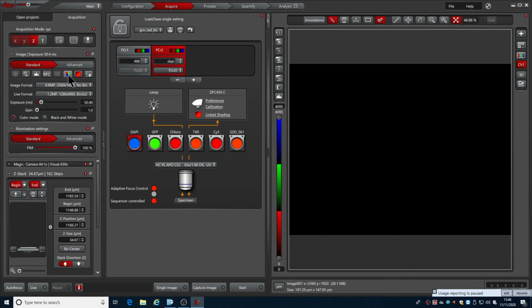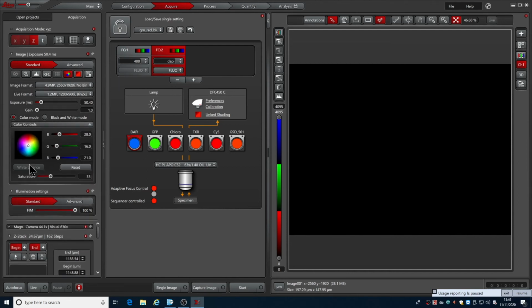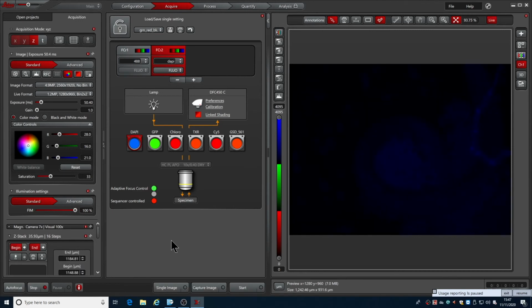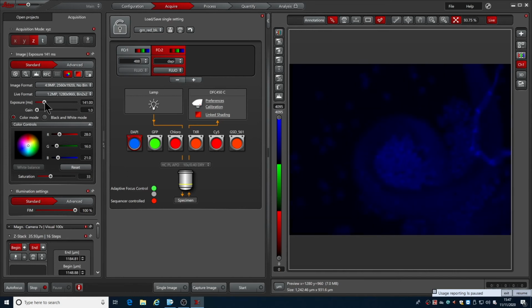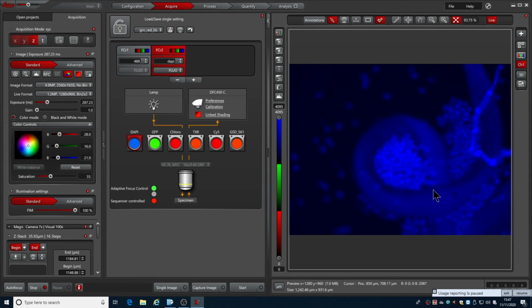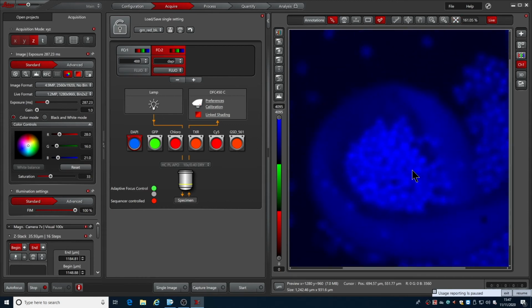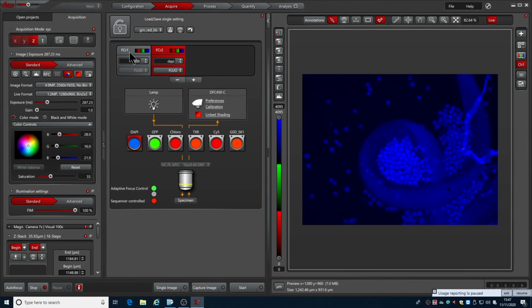It is often beneficial to check the camera colour balance. Do this by finding an area of the slide with no sample, defocus slightly, and then in the colour controls click White Balance, ensuring the light path is set back to camera. This is simplest to do by clicking Live. As before, set the exposure times for each channel before capturing your images. If you're only taking a bright field, then you only require one channel for the RGB image.